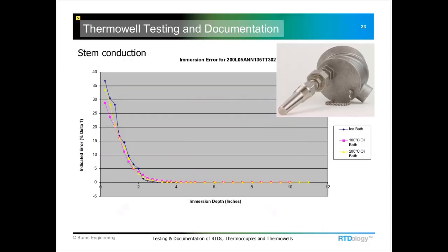So the immersion length required to get a good accurate temperature measurement can be one thing, and then the immersion length necessary to pass those strength and wake frequency calculations can be another completely different number. If we look down on this graph, the error here is the percentage of the delta T, so it's a percentage of the ambient conditions against the fluid temperature that you're measuring. And this one was done at 3 different temperatures: in ice, 100 degrees C, and 200 degrees C, and with a tapered Thermowell, which is shown in the photo here.